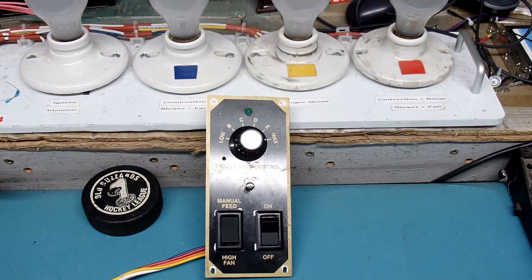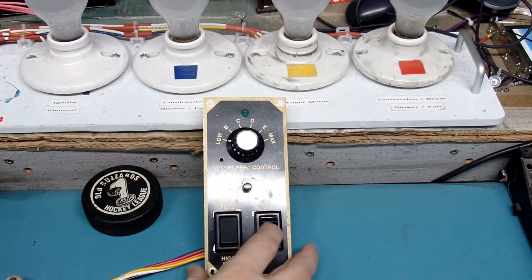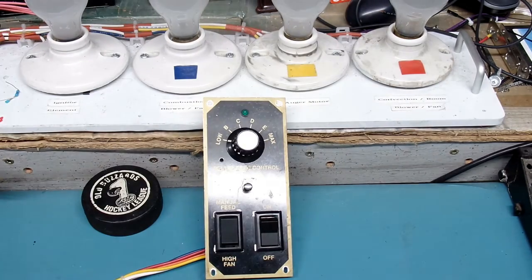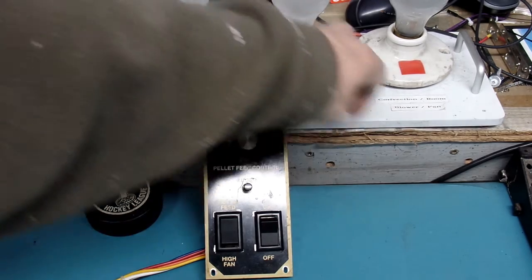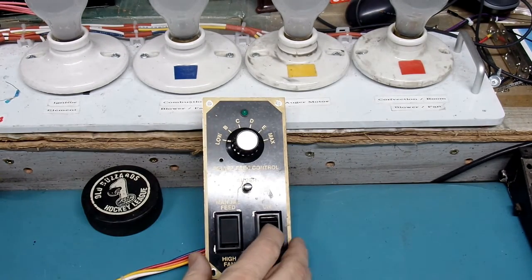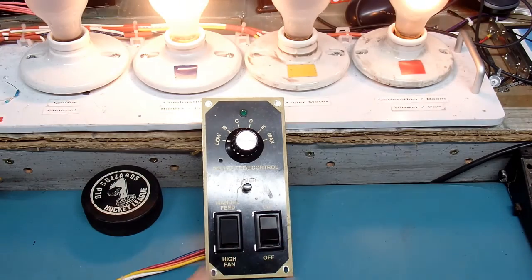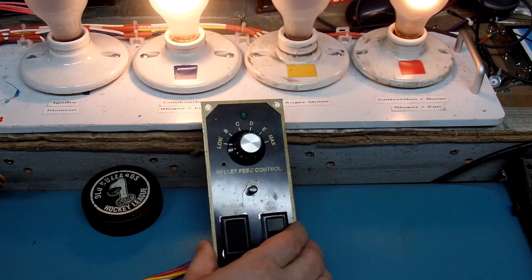In any case, we'll go through testing here just to make sure that everything is the way that it should be and that we're happy with the performance. So I'll set it to low to start with. I'll go ahead and turn it on. I have it connected to my tester, and my tester uses 3 different light bulbs to simulate the different features of the stove: the combustion fan, the auger motor, and the convection or room fan. So I'll go ahead and turn it on, and what should happen is the combustion fan and the convection fan, the room fan, should come on just like that. So that's functioning okay. I'm on low.